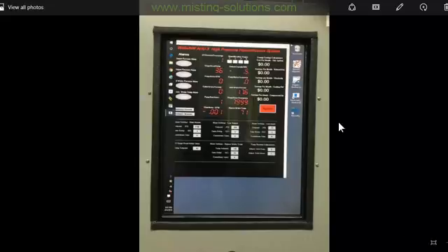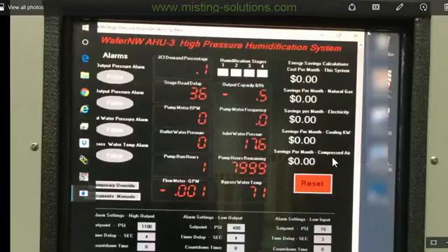And that concept is demonstrated right up here in these 4 different squares. When I zoom in here, you can see these are humidification stages, zone 1 through zone 4. You bring each stage on individually, 10%, 20%, 30%, 40%. Each one of these would have a red light on it when it is on. As soon as you get to stage 4, the red light's on. Then you bring on zone 1 again. Now you're on stage 5 or 50%. Then you shut off stage 1, turn on stage 2, you're at 60%. Shut off stage 2, turn on stage 3, 70%. That's all with stage 4 on all the time.